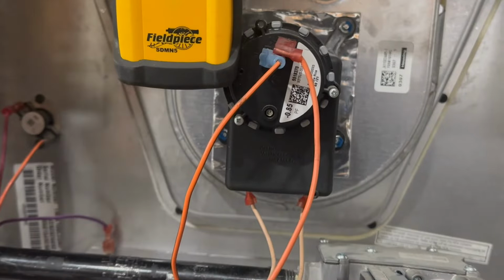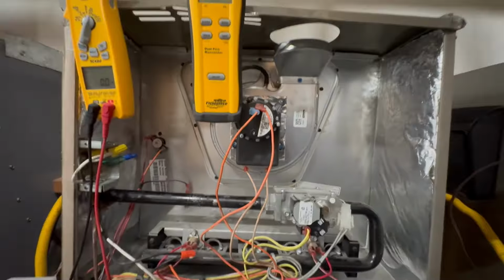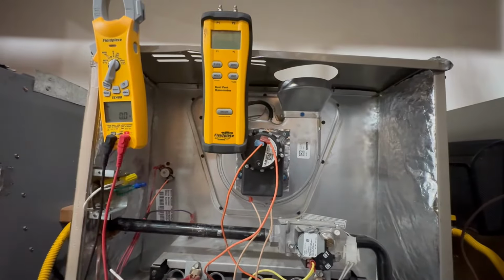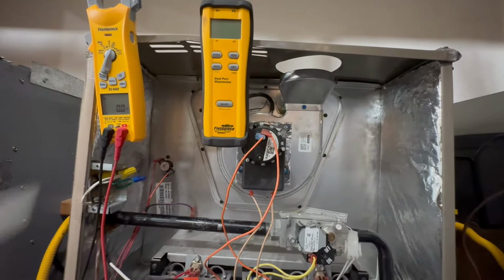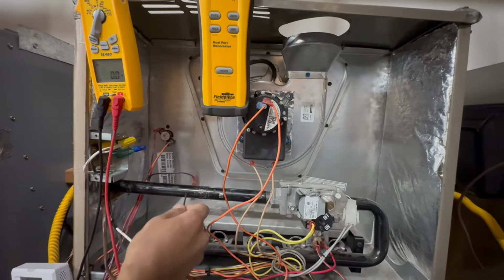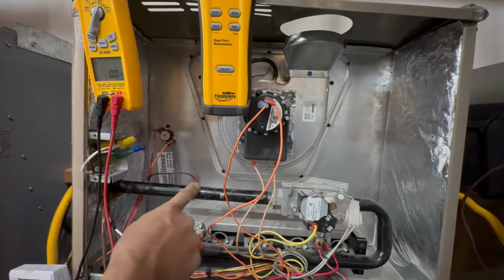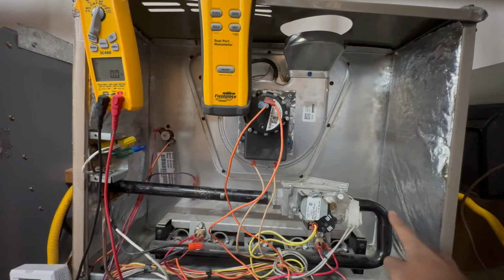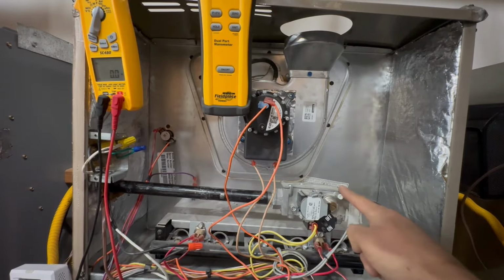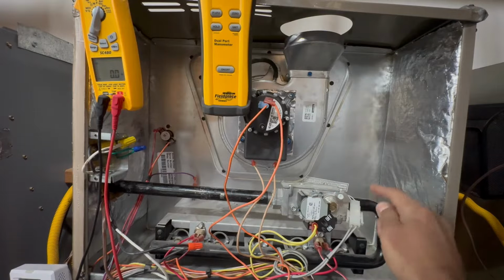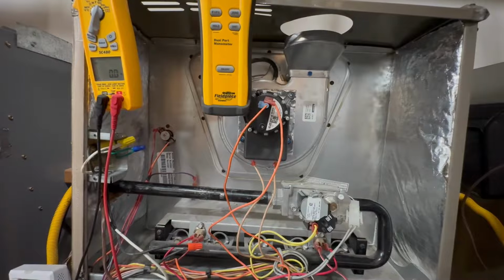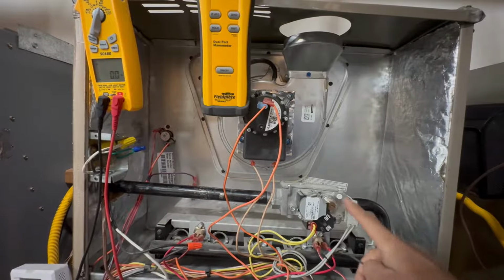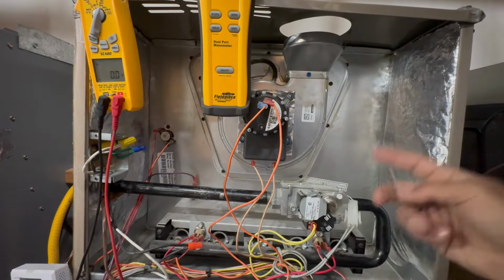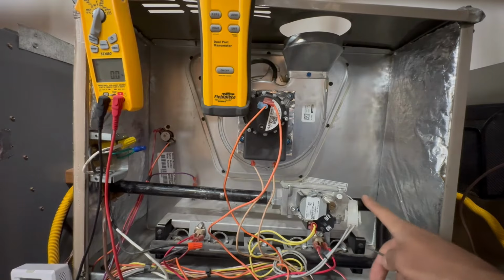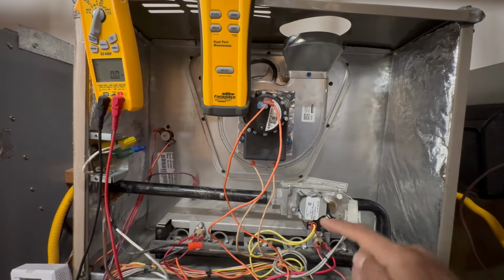So all right. Now, when it comes to the gas valve, yes, you do need a manometer. You got to be able to read inches of water column. So typically you have about 8 to 11 inches of water column coming from the city, and then outputting it should be about 3.5. Different gas valves, different manufacturers will probably say 3.4, 3.3, or 3 point something around that ballpark number. But 3.5 is usually a good number. And if it's a second stage heating, it normally will output 4.5 or a little bit higher to produce more BTUs. But I'm just going to show you how to check it.